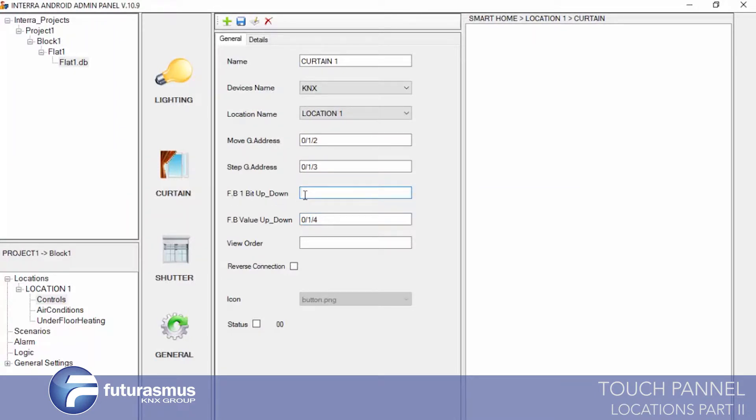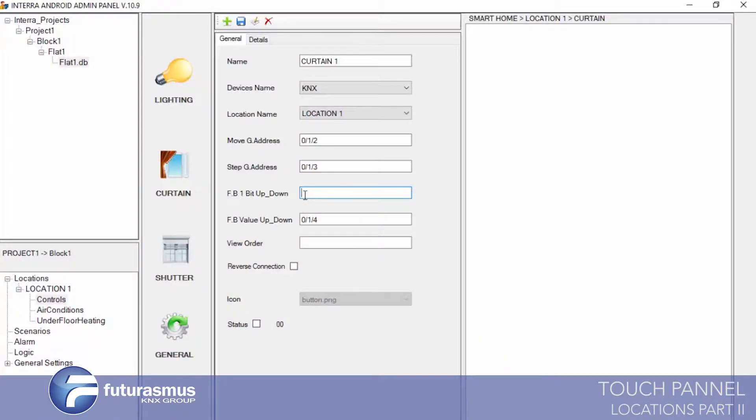We leave blank the feedback one-bit up/down address. It is used for completely open or completely closed, but it is not necessary because we define the value feedback address. It also gives us 0% open or 100% closed information, so we don't need the one-bit up or down value.